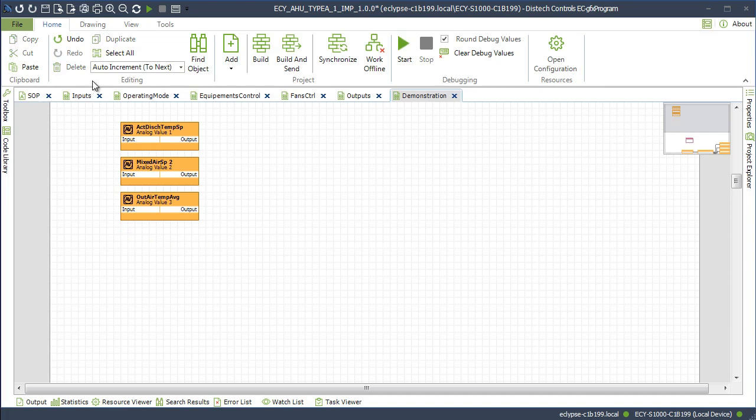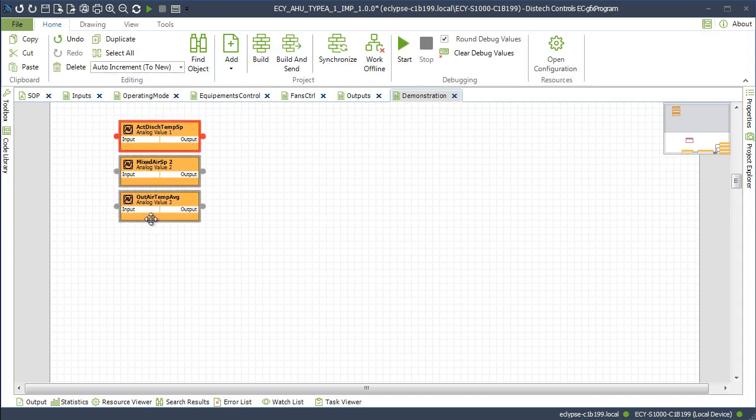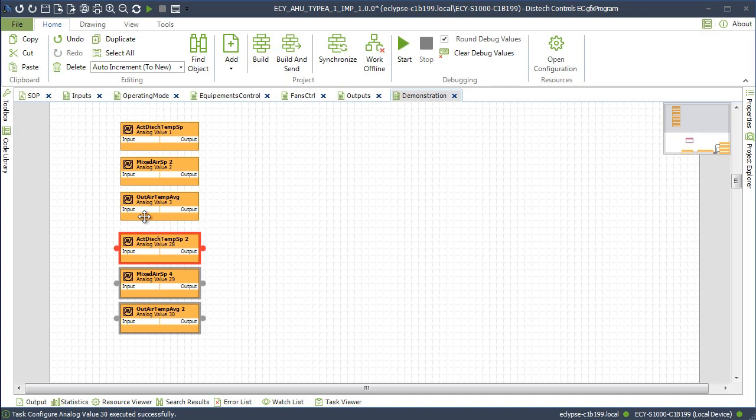When Auto Increment to New is set and you copy and paste resource blocks, the block number will automatically be incremented to the first available number that has no current configuration set in the Resources Configuration window. Because a configuration has been made for analog value block instances up to 27, these new blocks range from 28 to 30.